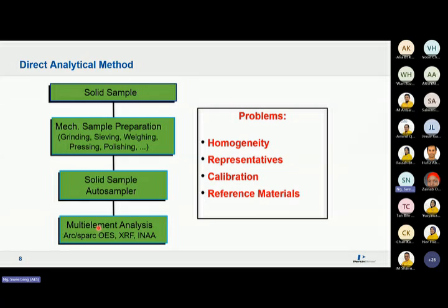If you don't make it a homogenized matrix, say I give you a geology example, you have a sediment and another material which is calcite. Calcite and sediment are different matrices. If we don't homogenize them to become a similar matrix, we will have a problem with the calibration curve.